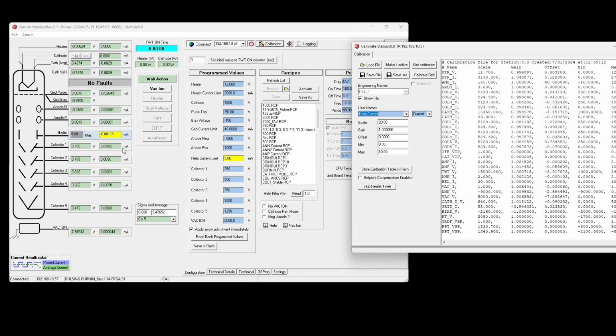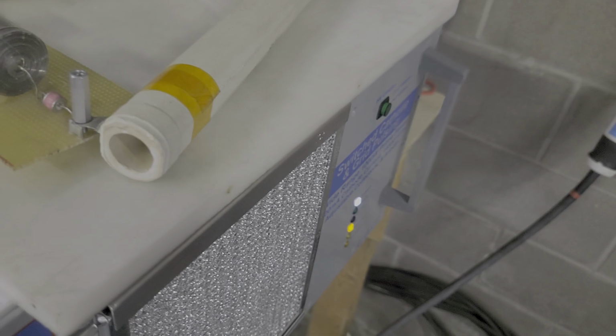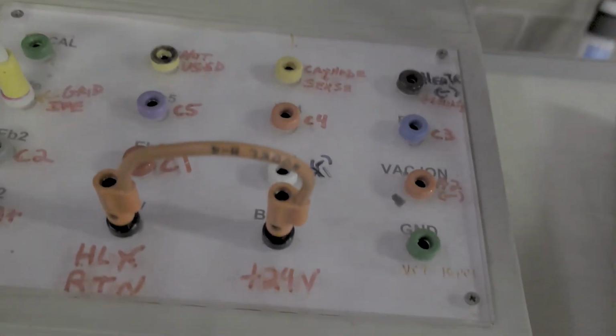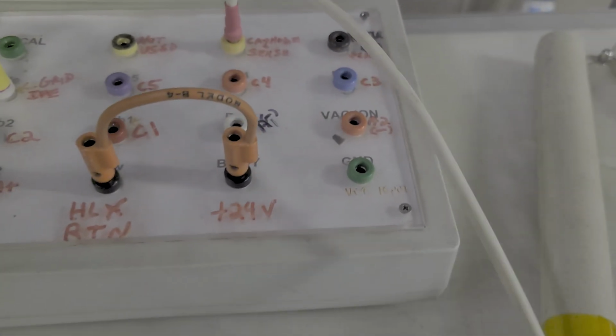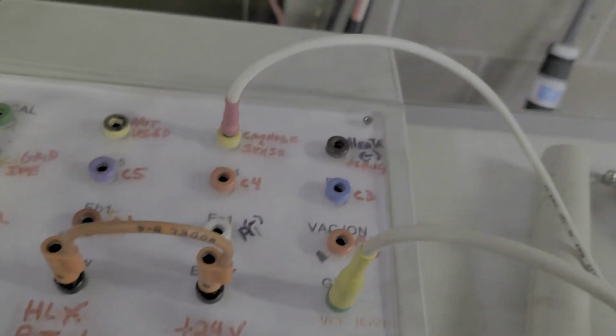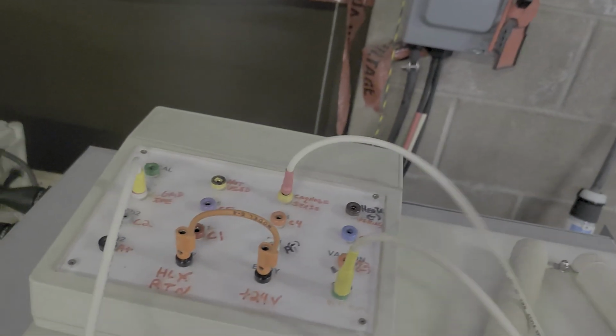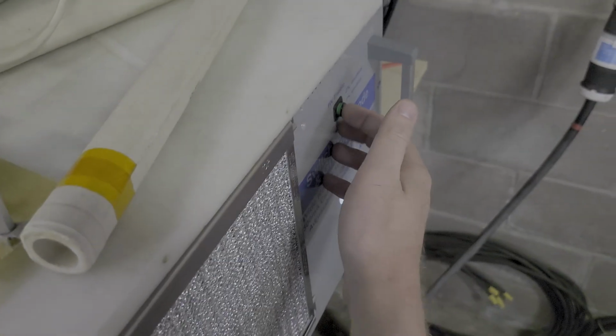The reason we ground the cathode is, one, for safety, and two, it also stabilizes the measurements of the bias and pulse top voltages so that there's not a lot of drift and we can calculate our gain and offset accordingly. So I'll be right back. Emergency off switch. And on this breakout box I have cathode right there and I have ground right there. Now cathode is grounded. Re-enable, and I'm going to start it back up from the office.